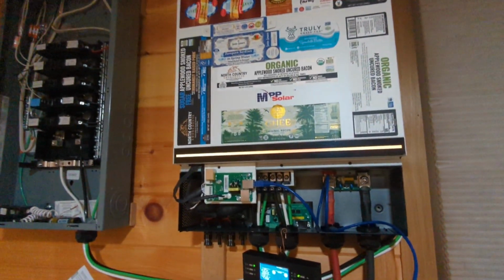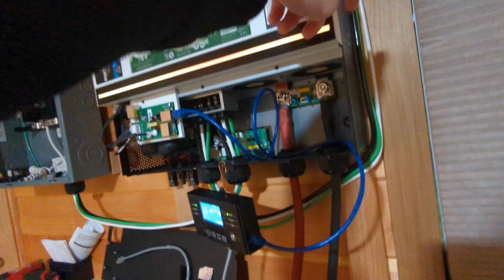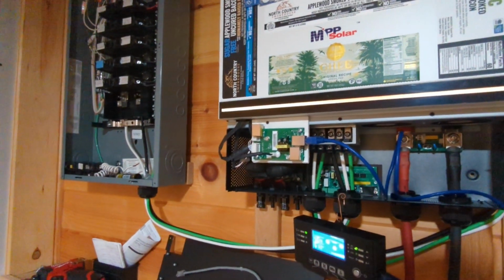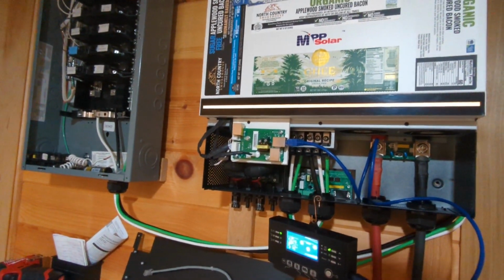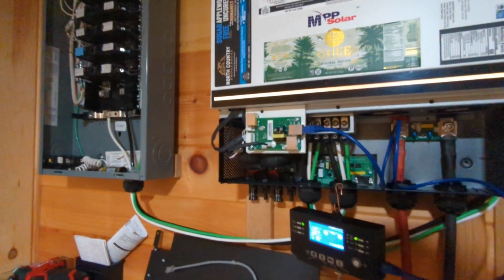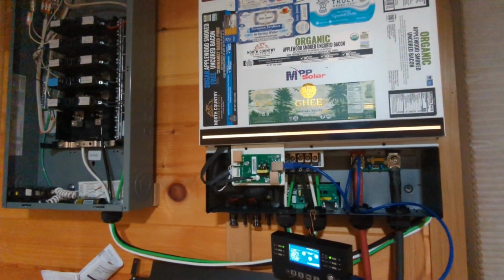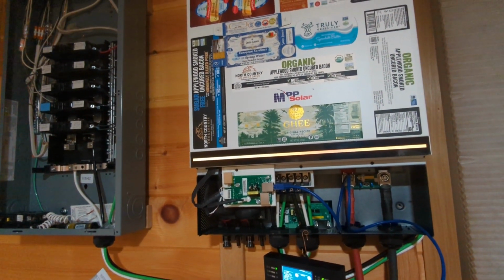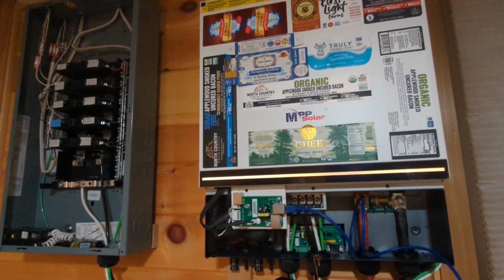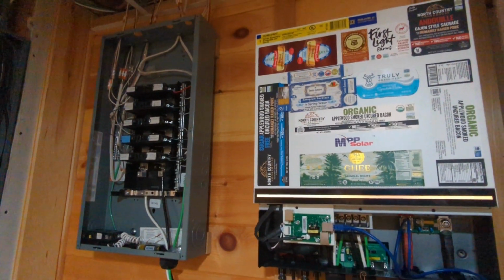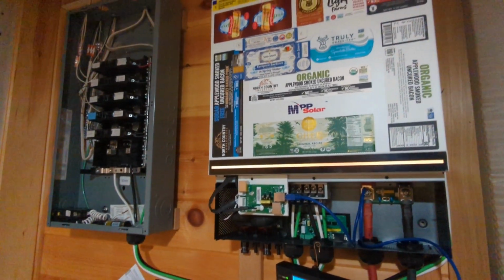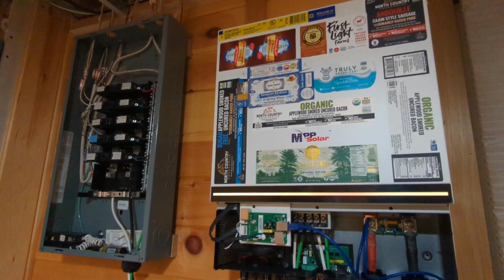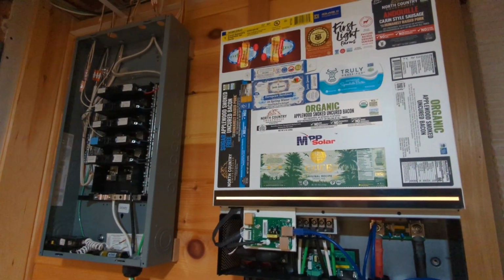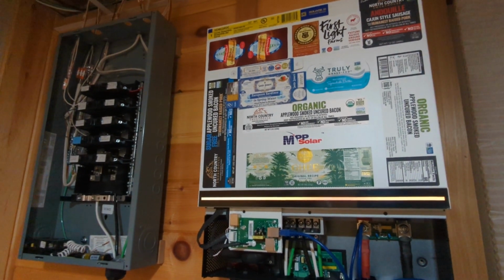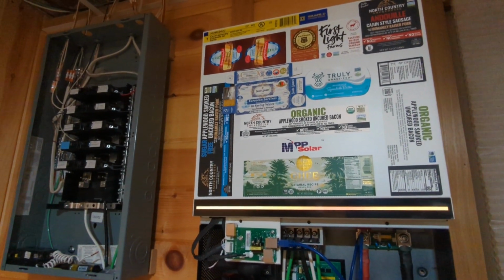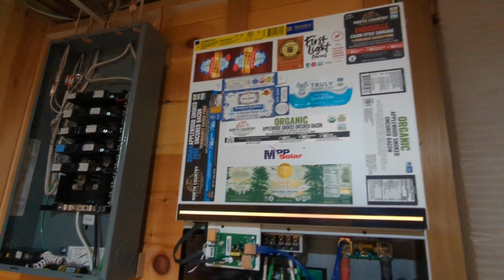Usually dust likes to stick in areas that don't have proper airflow. For example, in the very corners of the inverters, down on the edges, those areas tend to build up more dust and general debris. The fan blades also catch a lot of it, so I take the cover off and clean it out with an air compressor powered by another portable power station, a separate all-in-one unit. I disconnect power to the inverter and switch it off because I don't want to be touching electrical stuff with the cover open and messing around in there.